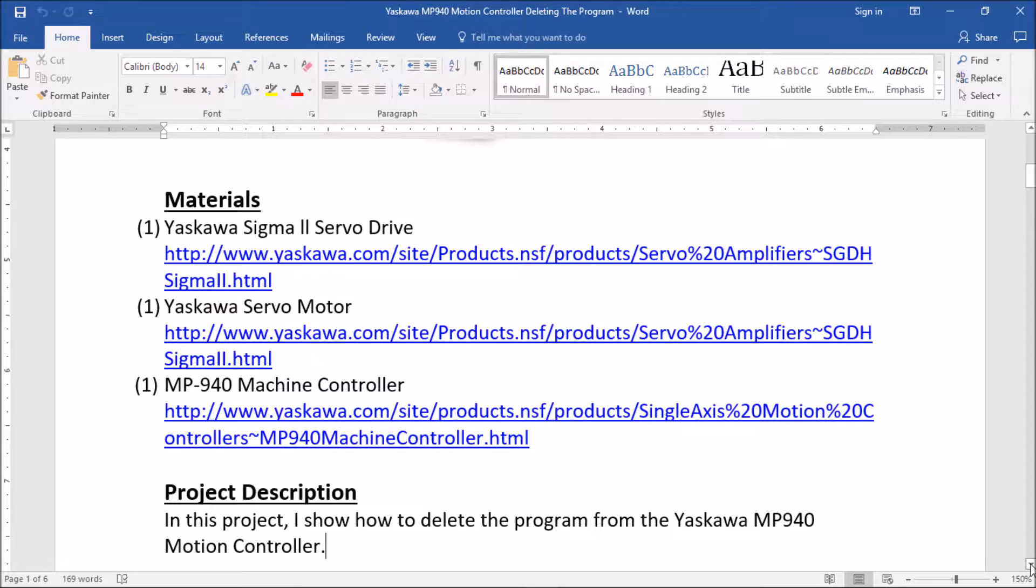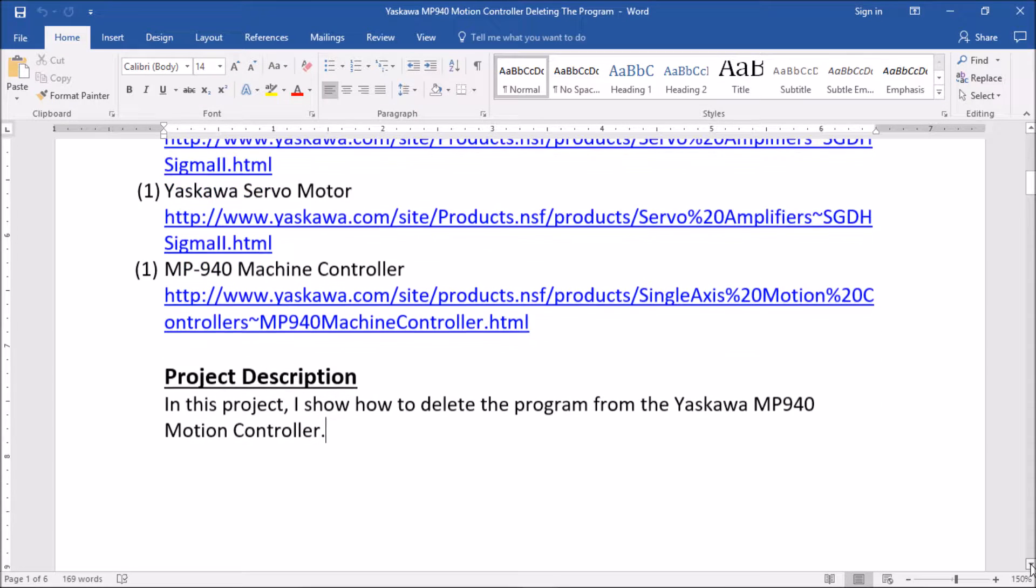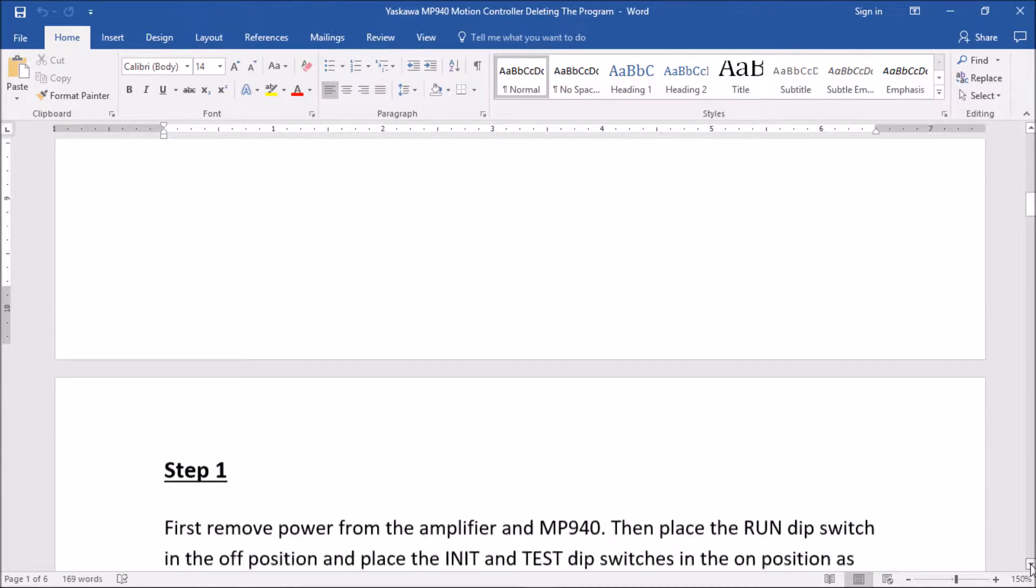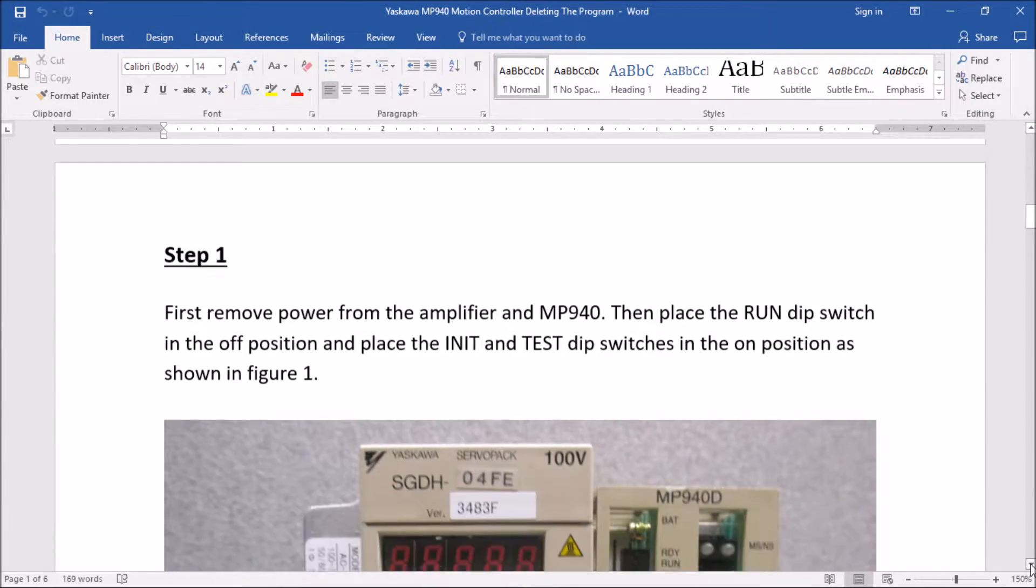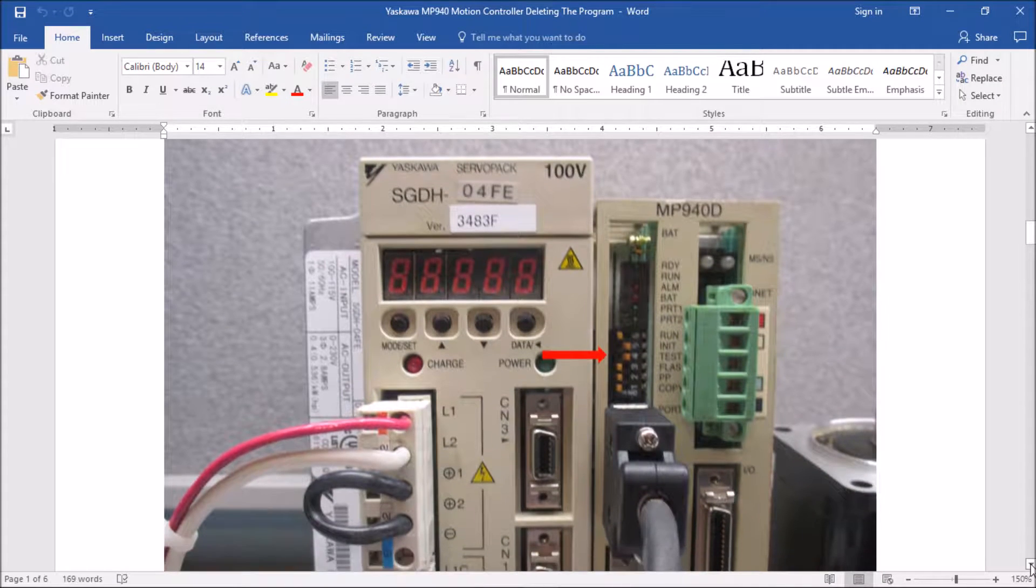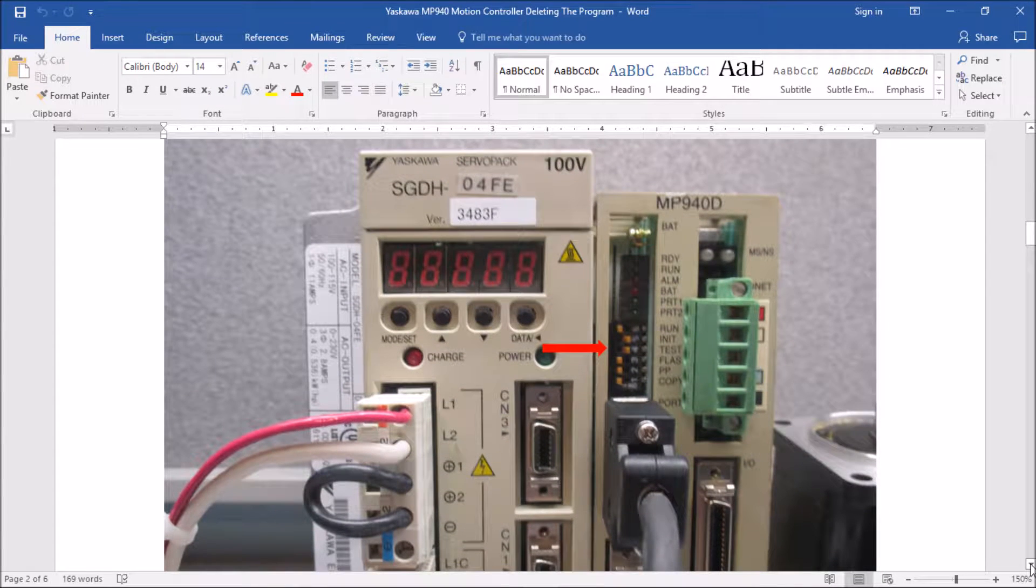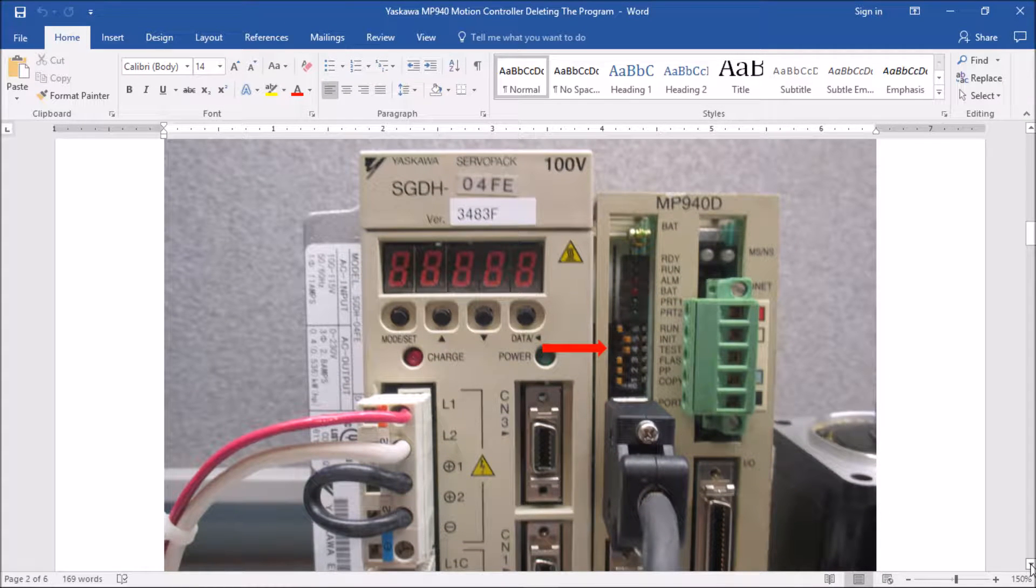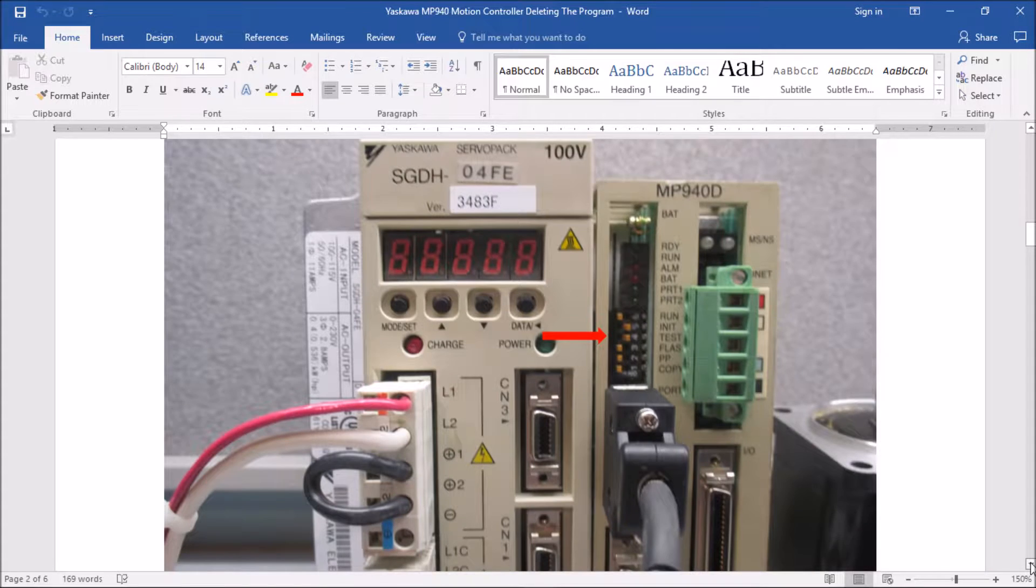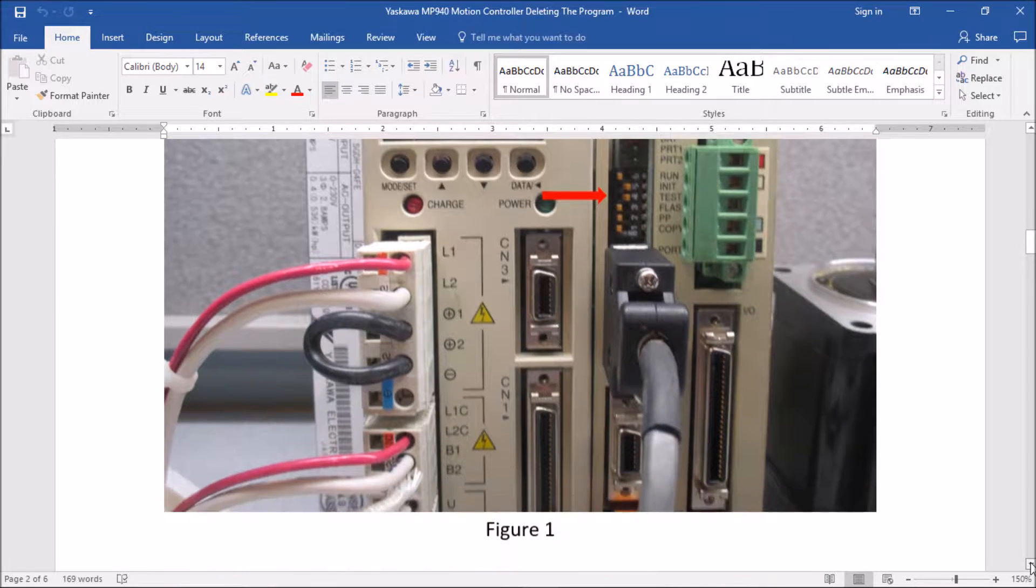Now I'm going to continue down here to step one. Here in step one I'm going to remove power from the system and place dip switches four and five into the on position. Now this is the test and the init dip switches, and all the rest of the dip switches are going to be in the off position. I'm going to continue down to step two.